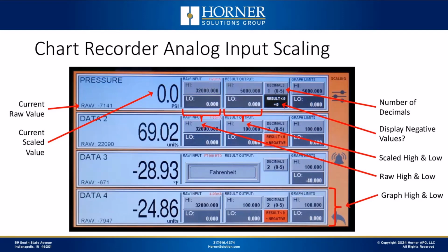And then the next column over, you can configure the minimum and maximum engineering units. So for 10 to 100 pounds per square inch, our minimum or low would be 10, and our max or high would be 100. And these are floating point values, so you're going to get good resolution and good results on the scaling. And then you've got a couple of things you can configure. You can configure how many decimal points you want to display on the screen, how many digits to the right of that decimal point. And if you get a slightly negative value as a calculation, is that something you want to display as a slightly negative value, or do you just want to display that as a 0? Sometimes that can happen at the very low end of a sensor. Its output may be slightly below 4 milliamps, for instance, and it might be interpreted as a negative in that case. But you can handle all that.